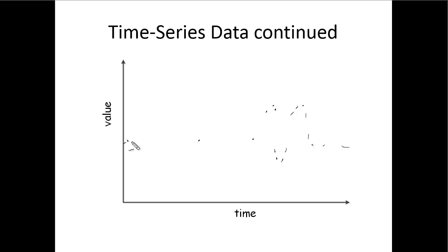Okay, and then I'm going to reconstruct my signal line, and it's going to go like that. So this would be compression using that swinging boxcar algorithm. During times when the data is not very dynamic, I'm not using a lot of space to store the information, and during periods of time when it is very dynamic, I'm using my database storage to capture that dynamicism.